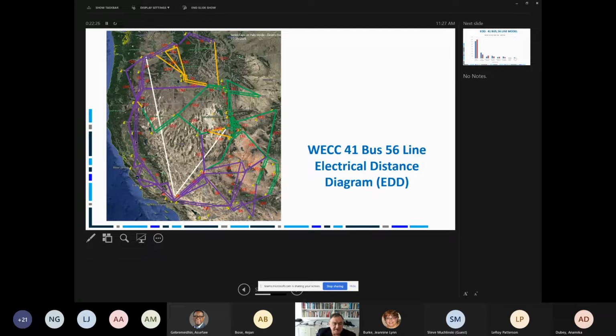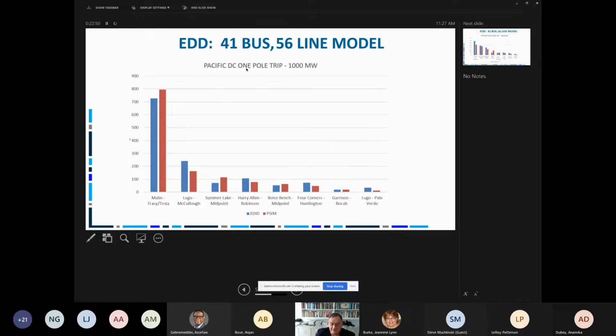So the impedance of a 500 kV line typically is about 0.0002, and the impedance of a 230 is about 6 times that. So basically what we do is we convert everything to a standard distance, and with a 41 bus 56 line model, I can simulate pretty accurately the trip of the Pacific.